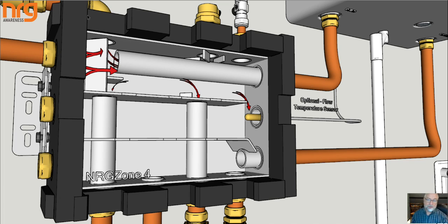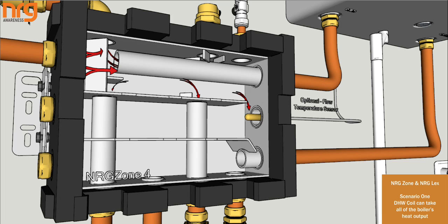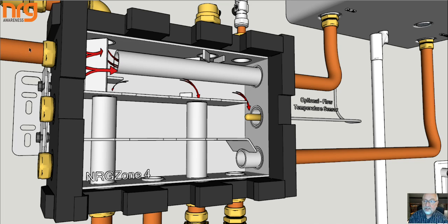So there are three scenarios. One is that the boiler and the pump for the hot water circuit are correctly sized for a coil, and so you have your reduced temperature water come back with your delta T drop from the cylinder, and that'll work. The second scenario is where the coil is not big enough, where there's a surplus of energy leaving the boiler, but the coil is at a designed size to do whatever it's doing. If there's any energy left over, it'll go through the coil and come back out, but also any water that hasn't been taken by the pump, because it wasn't necessary to set the pump high, will divert back on itself and still carry on and feed the zones.